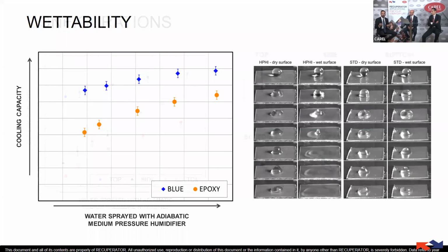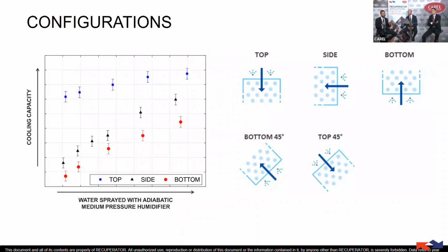plate exchanger. Of course, it's really important, as we have seen, to wet the heat exchanger as much as possible. The heat exchanger also works like a water drop separator, because we have seen before that the geometries should be able to create turbulence in the air. Then it's important to exploit gravity to wet the plate as much as possible, so that we increase the cooling capacity more and more. On the left, we have a picture that shows the performance behavior of different configurations. The main three are top, side, and bottom, where the top configuration is where we exploit gravity completely.